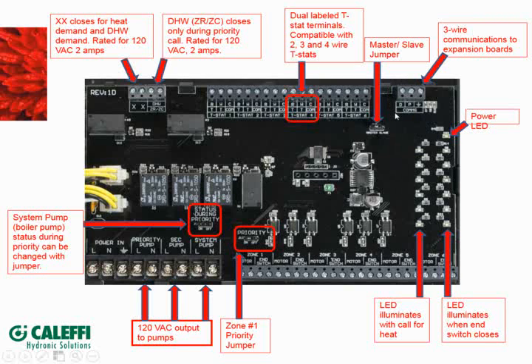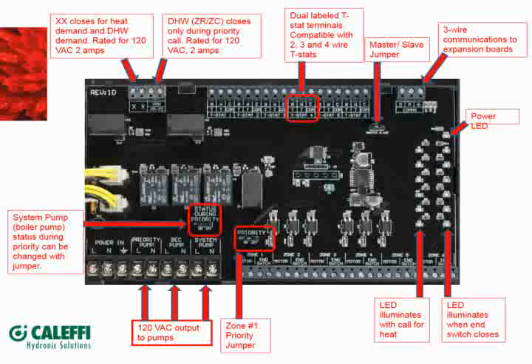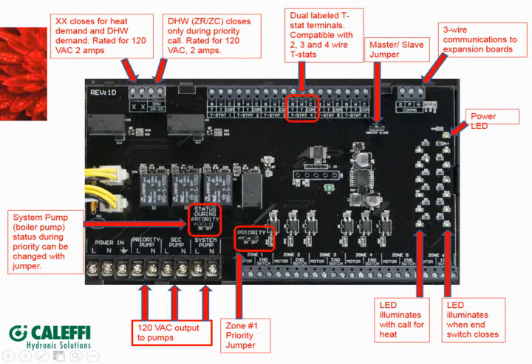So again, up here, 3-wire communications, the same. One thing to note, that the valve box will communicate with a pump box, so you can kind of mix and match these controls. We'll show a schematic on that later. I don't think it's a very common thing, but if you get into a funny situation where you would need to have that done, you can do it. We again have a power LED, and then we have LEDs that illuminate with the call for heat. That's this row here. So when the thermostat calls, you'll see 1 through 6, whichever one it is, light up. And then there's an LED that shows when the end switch on the zone valve has closed.